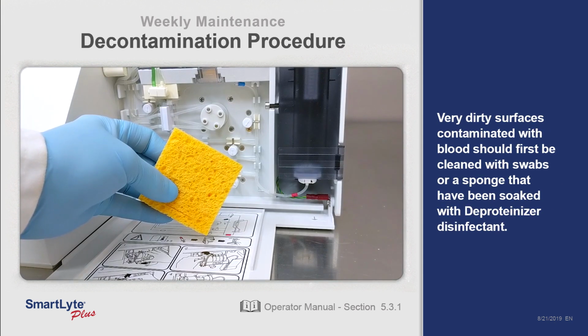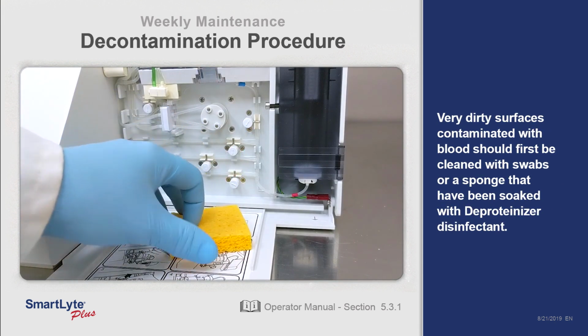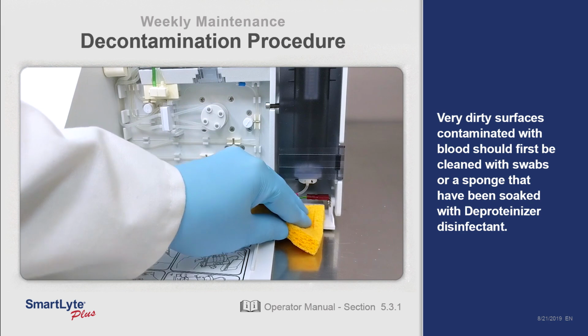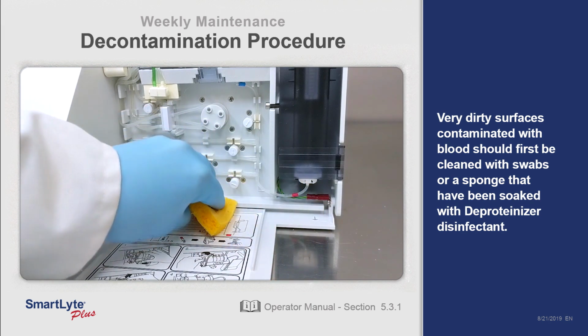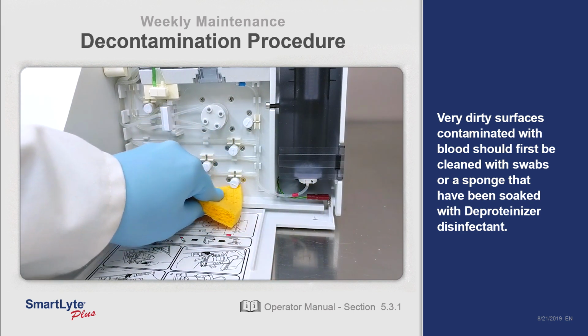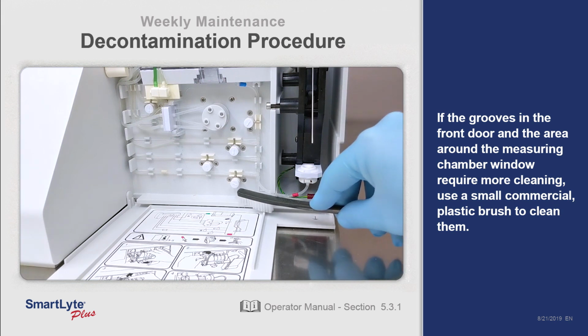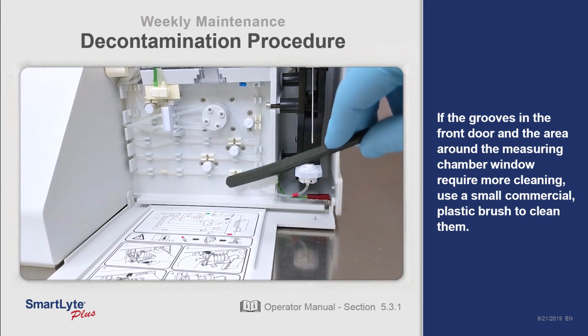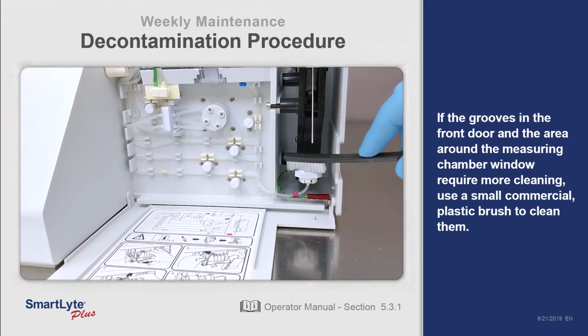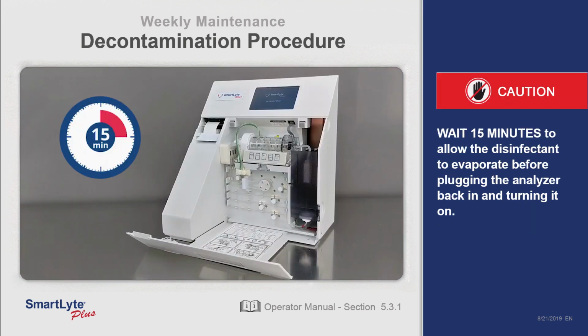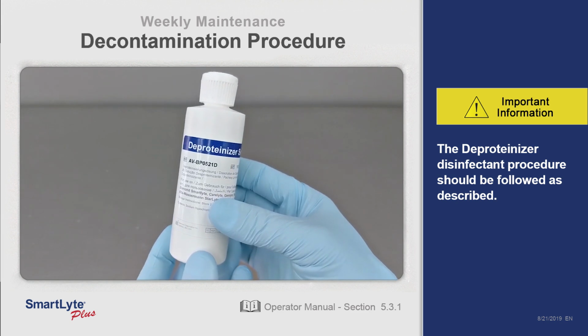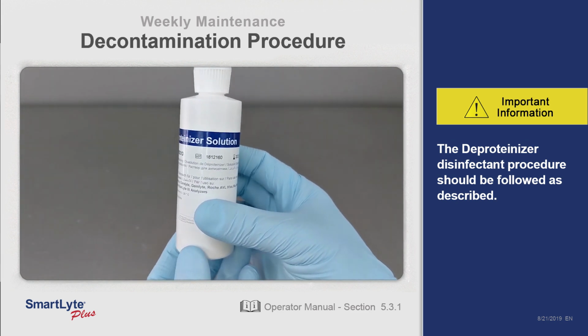Very dirty surfaces contaminated with blood should first be cleaned with swabs or a sponge that have been soaked with deproteinizer disinfectant. If the grooves in the front door and the area around the measuring chamber window require more cleaning, use a small commercial plastic brush to clean them. Wait 15 minutes to allow the disinfectant to evaporate before plugging the analyzer back in and turning it on. The deproteinizer disinfectant procedure should be followed as described.